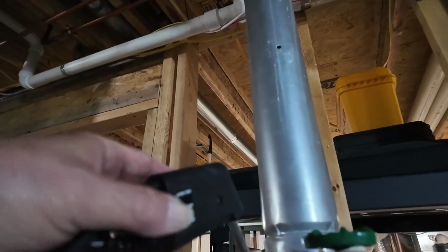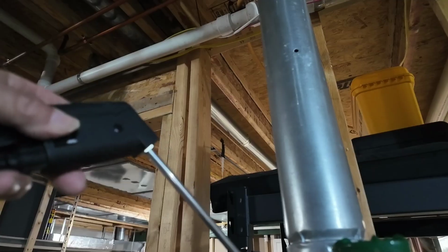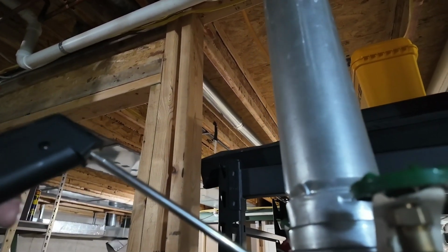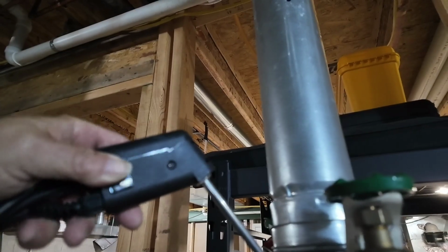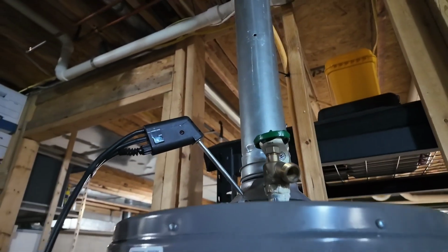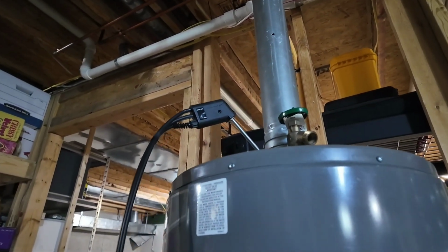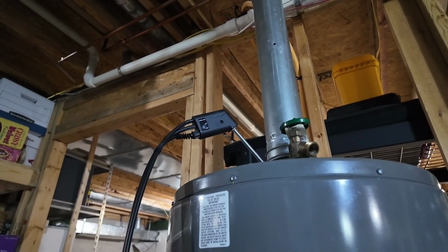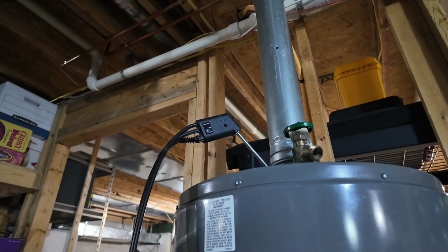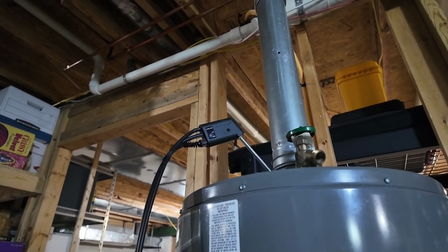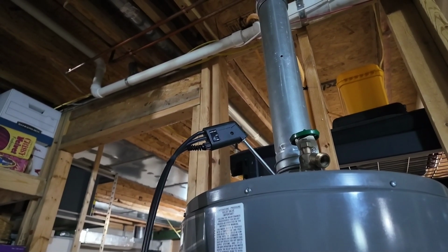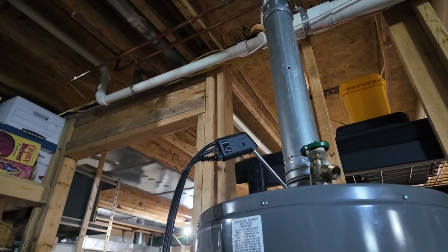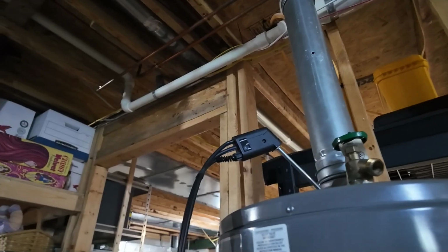I'm going to move this combustion analyzer wand over to the other side. And if you can notice, I'm going down into the throat. That's undiluted. And we saw some more movement over here. I'm going to allow it to stabilize. And we're at 49 parts per million.